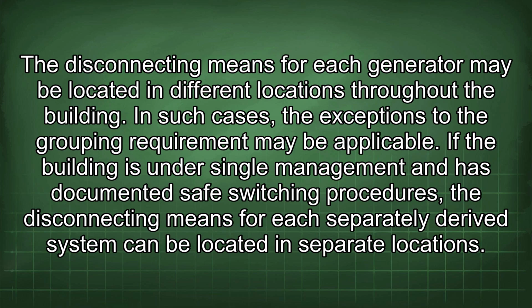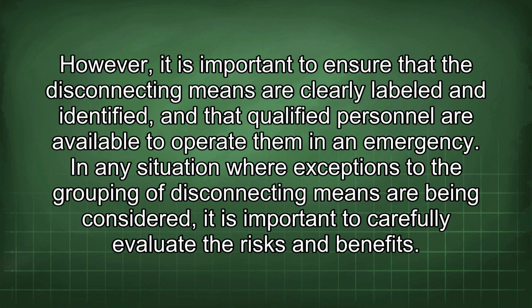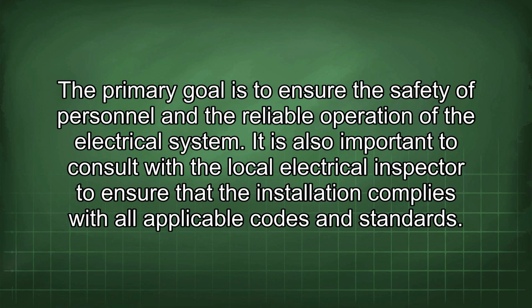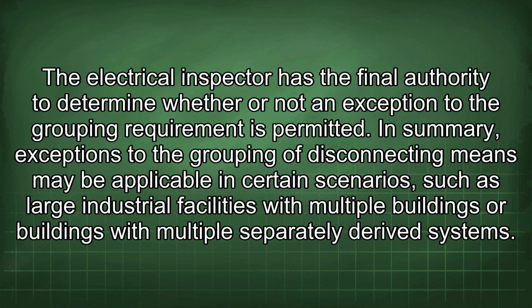If the building is under single management and has documented safe switching procedures, the disconnecting means for each separately derived system can be located in separate locations. However, it is important to ensure that the disconnecting means are clearly labeled and identified, and that qualified personnel are available to operate them in an emergency. In any situation where exceptions to the grouping of disconnecting means are being considered, it is important to carefully evaluate the risks and benefits. The primary goal is to ensure the safety of personnel and the reliable operation of the electrical system. It is also important to consult with a local electrical inspector to ensure that the installation complies with all applicable codes and standards. The electrical inspector has the final authority to determine whether or not an exception to the grouping requirement is permitted.